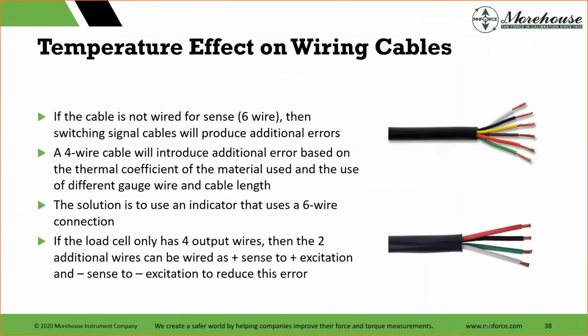Same with load cells. In several of these meters, there's a 4-wire cable. You have resistance of the cable, and you're not feeding back the sense lines. That introduces an additional error based on the thermal coefficient of the material used, the gauge of wire, and cable length. So if someone cuts a cable in half, or you have an oops moment in shipping where someone patches a cable, you could very much change the resistance depending on how much gets cut out, which will change the output. And those errors can be as high as 0.1% or higher. It just depends on gauge factor, how long it is, and other factors.